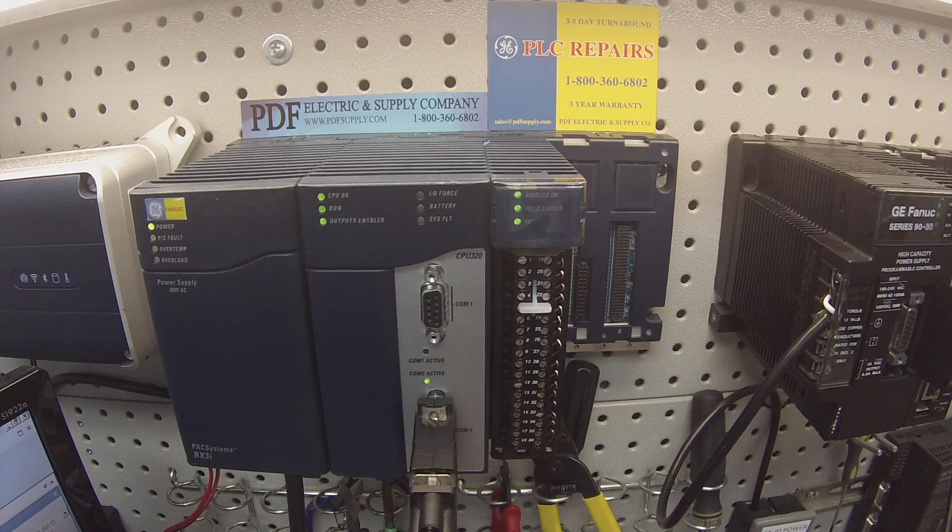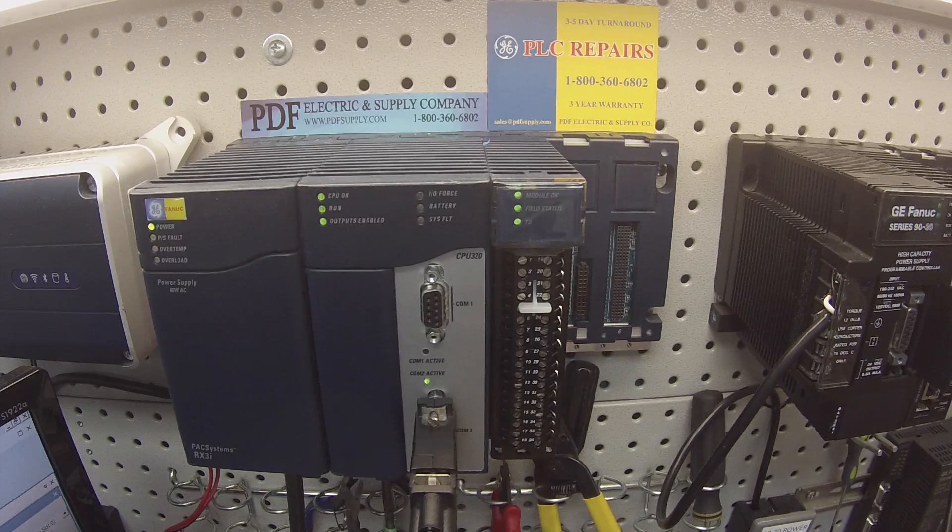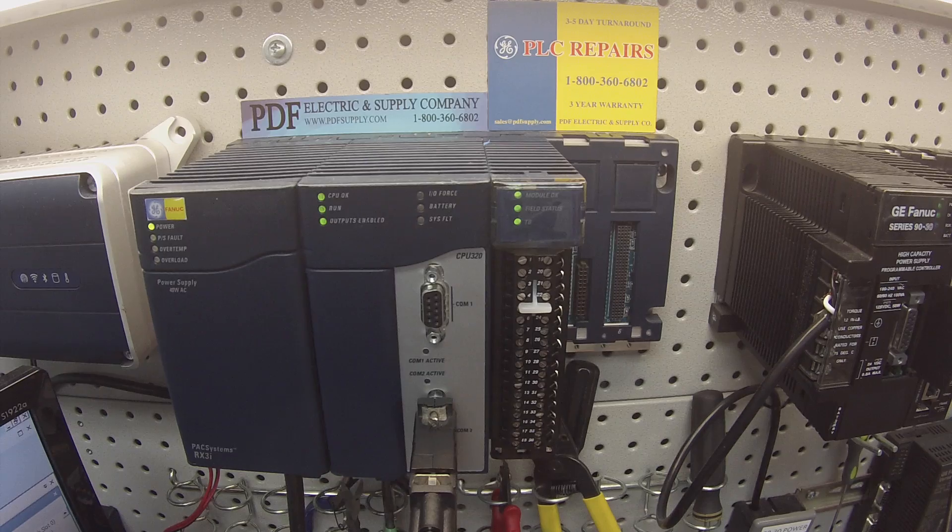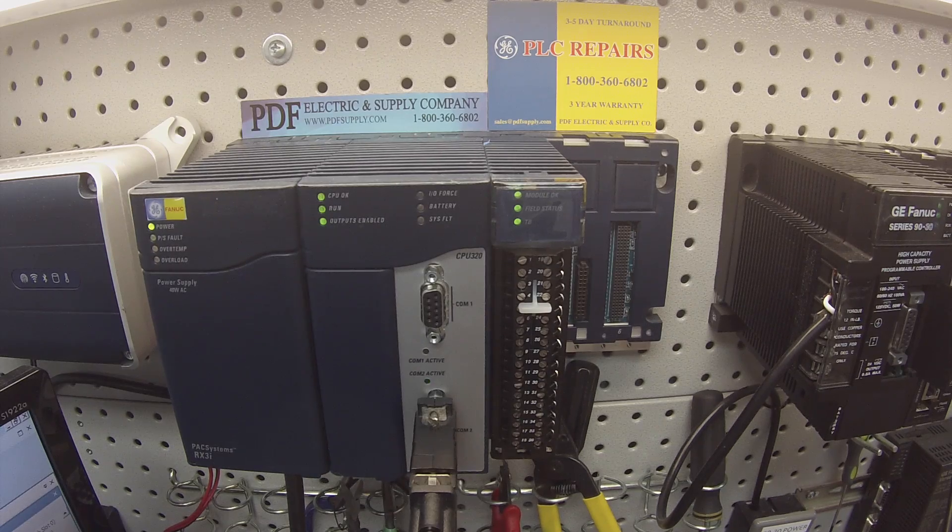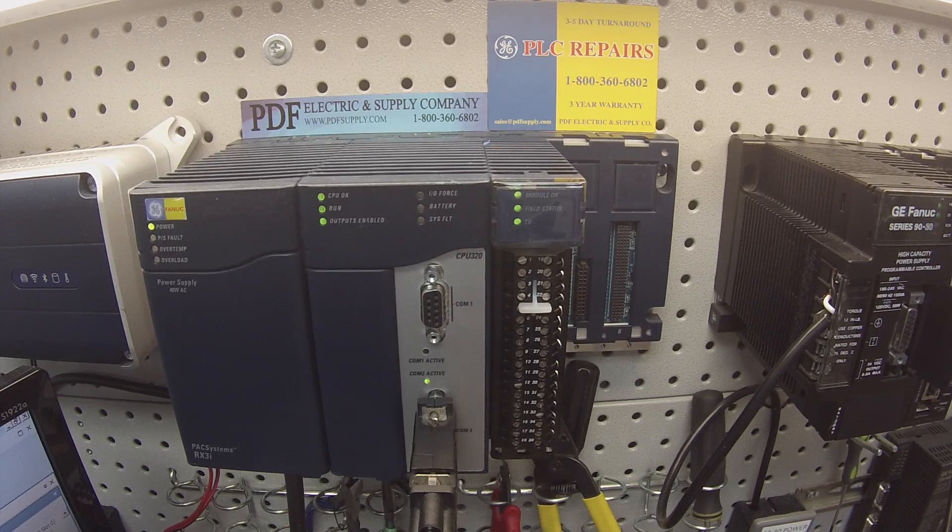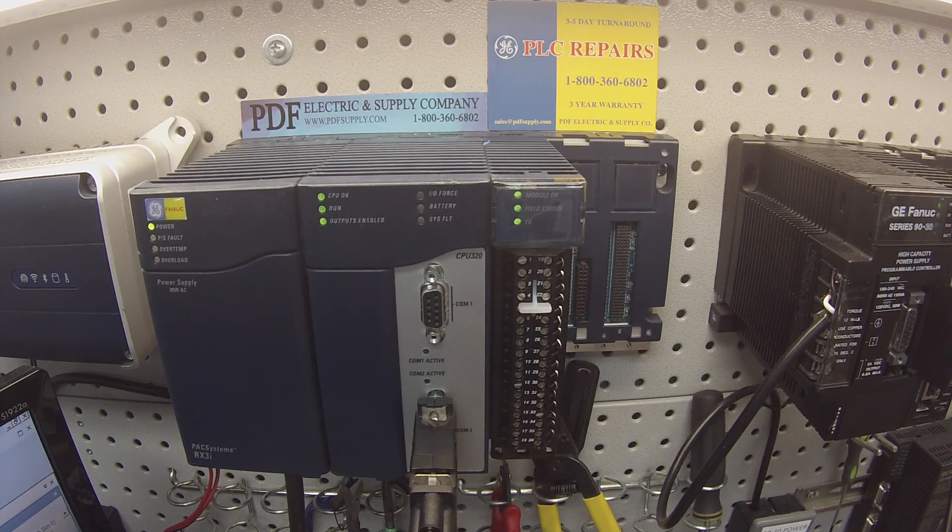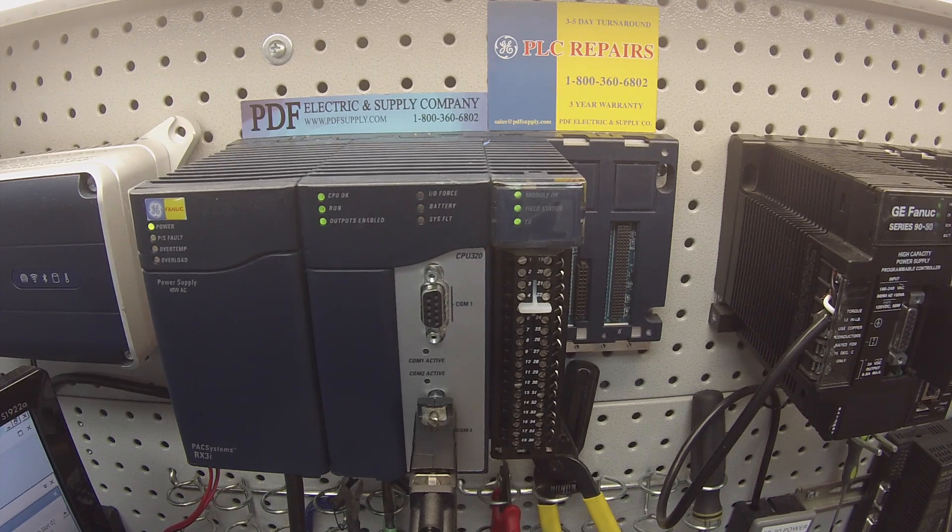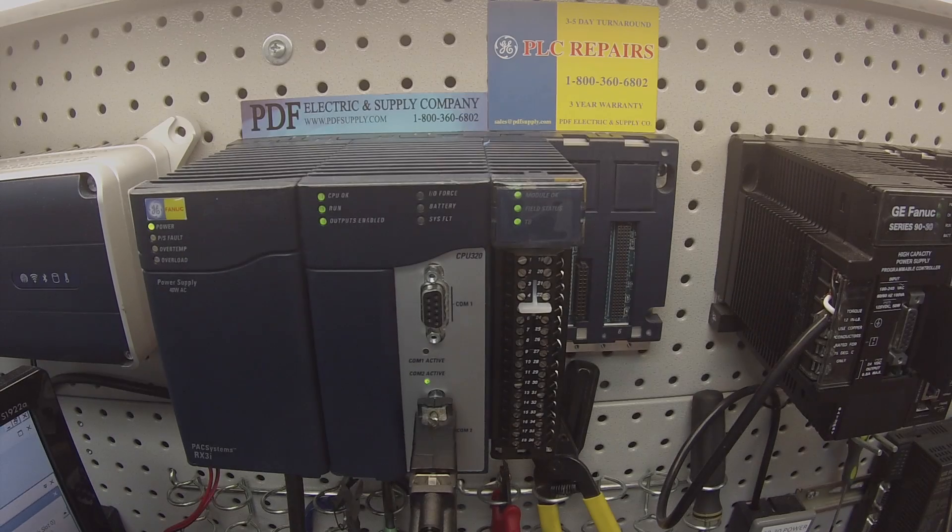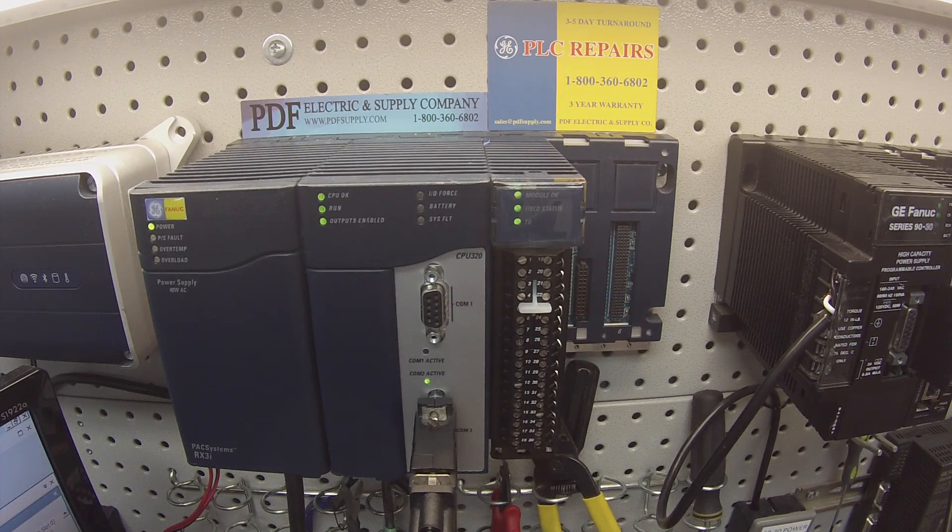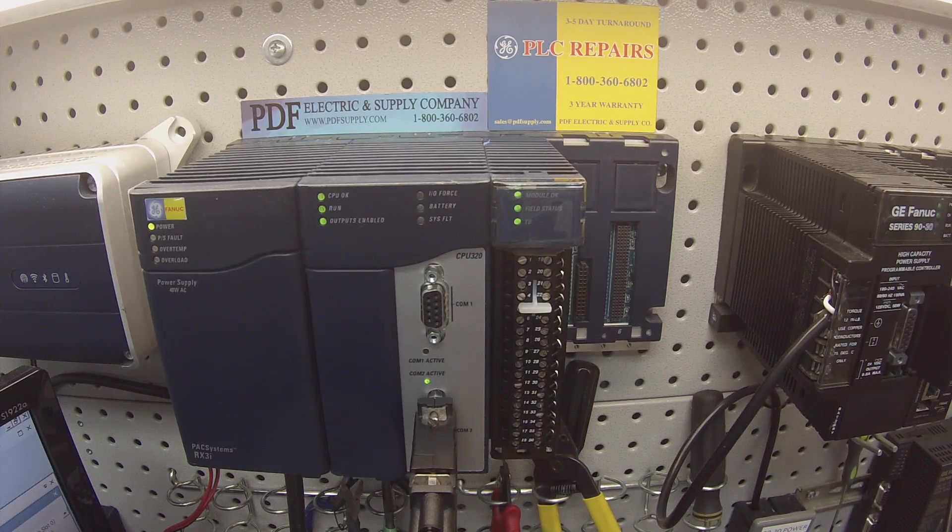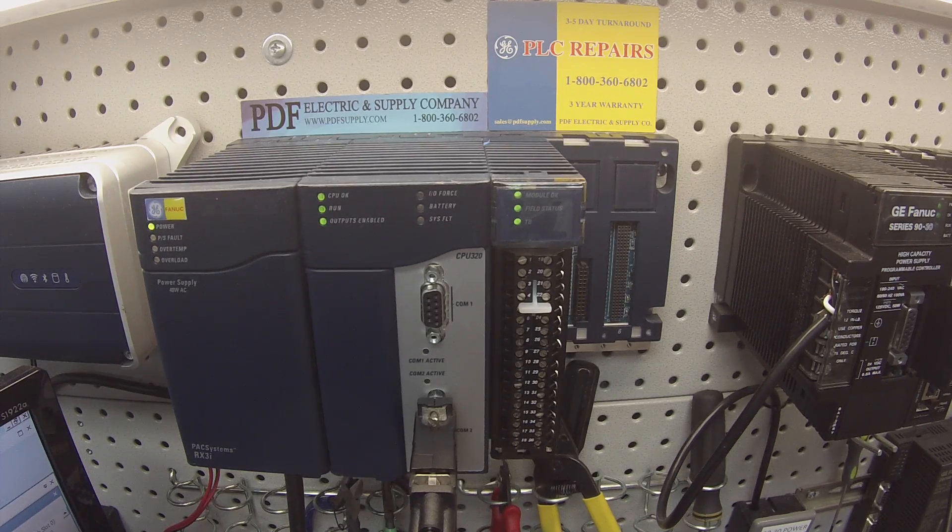As a quick recap: from the beginning when you plug the module into the rack, you should have a blinking module OK light on. When the terminal strip is completely fastened to the module with the lever in the upright position, your field status and your terminal block LEDs should both be on in green. When you're probing each channel, whether you're using voltage DC or milliamps DC depending on your needs, you need to make sure that you have first a working circuit, a working channel. Two, that the channel is stable. And three, that the channel is not immediately giving you full value when you may not be actually giving it a full value of 10 volt or a full value of 20 milliamps. Keep in mind that they do tend to or occasionally fail at full value. That's a problem.